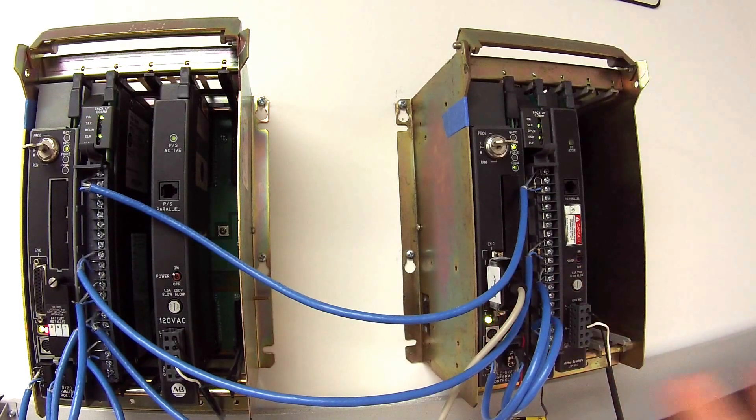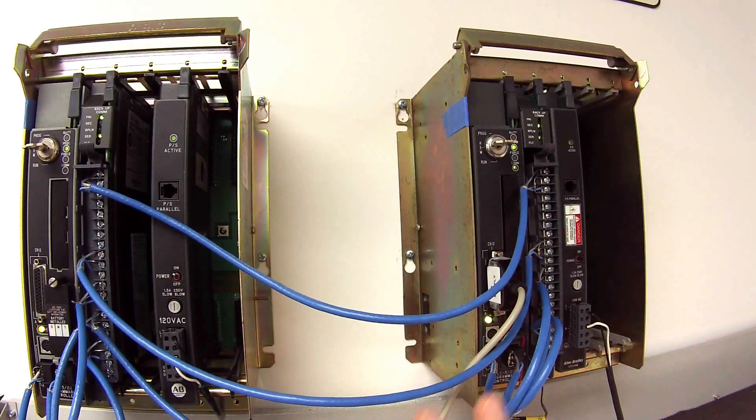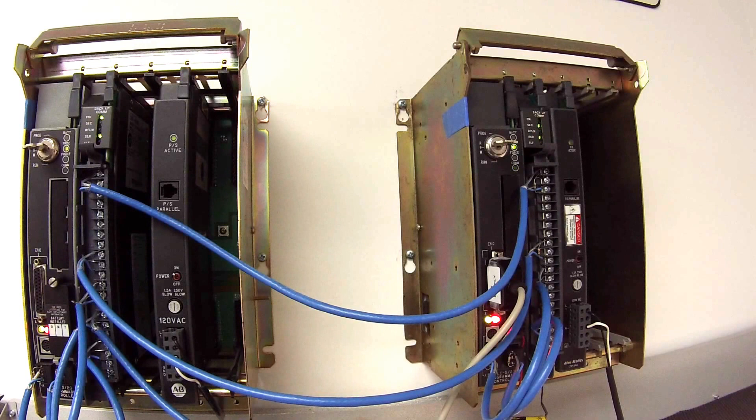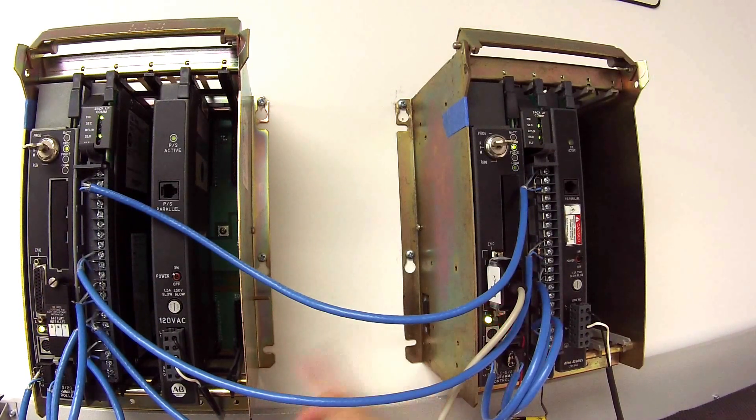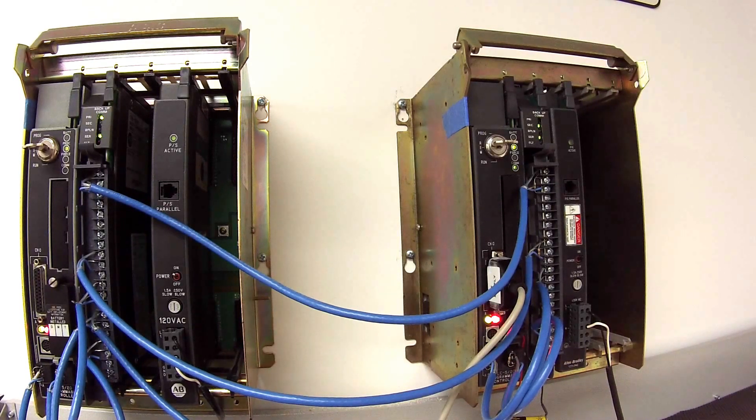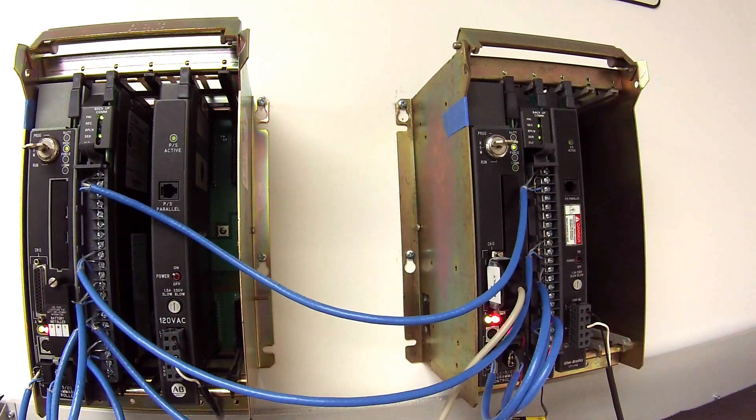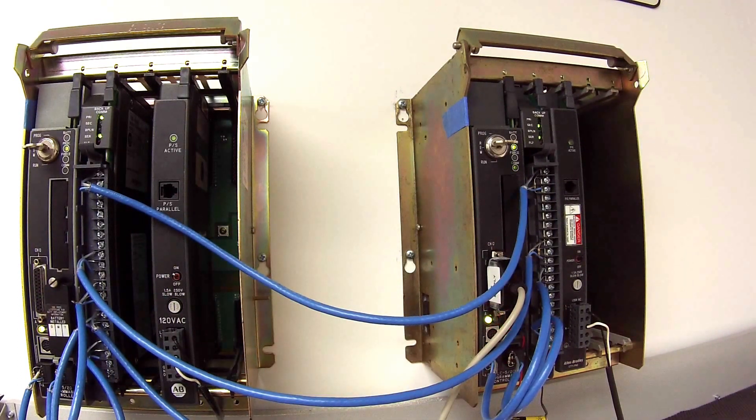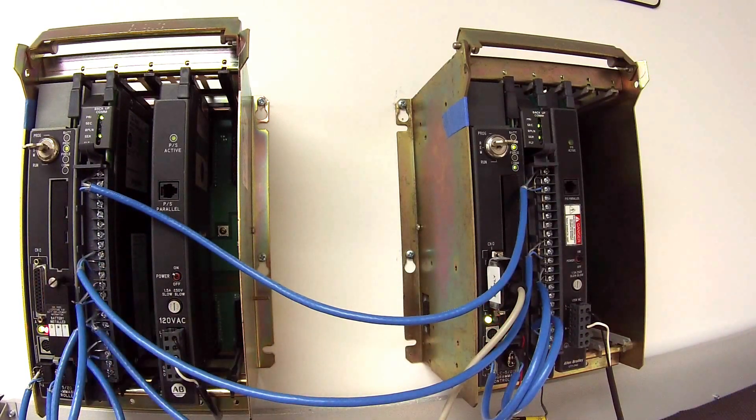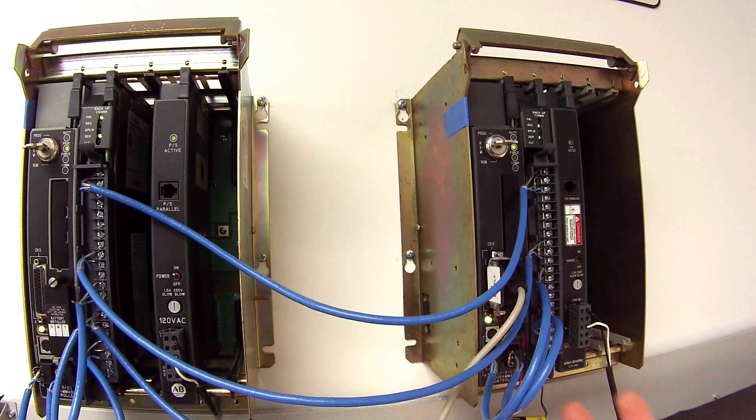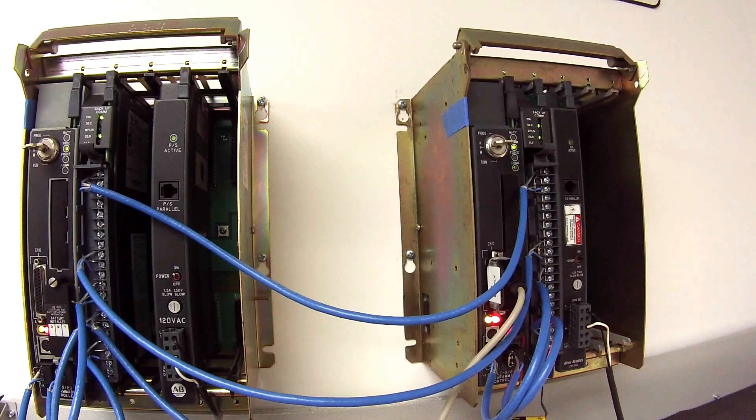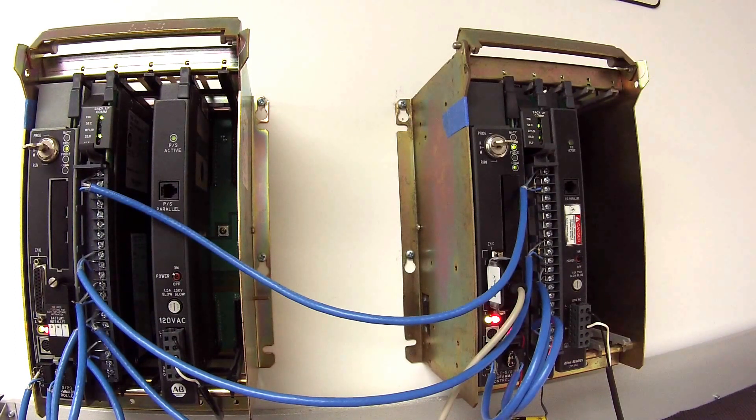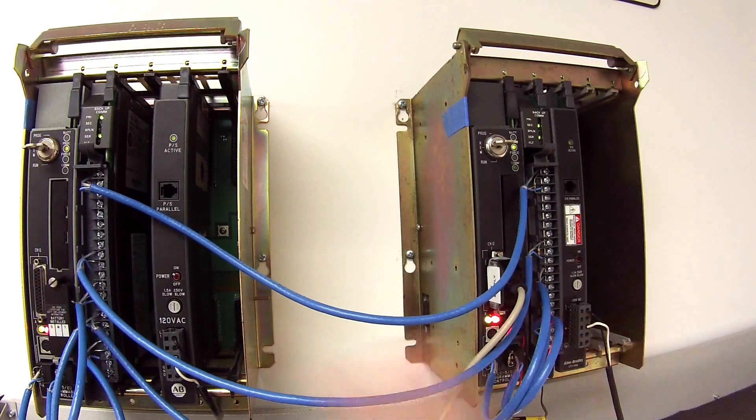I have two racks set up as just my test lab here. This is probably a smaller version of what you have in the field, but there are two 1771 A1B four-slot chassis. They're being powered by 1771 P4S power supplies, and the processors are 1785 L20B Series E. They're both L20B Series E. They don't have to be, in the field you may have an L20 on one side and an L40 or 60 or 80 on the other side, it doesn't matter. What's important is that they're both communicating on the same data highway address. That's one tip for you.